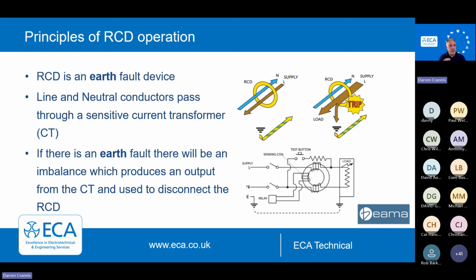And there are different levels that RCDs can handle with this, from the type AC, which is virtually nothing, up to type A's, B's, F's. They have more tolerance in that window. But that's essentially how an RCD works. With 30 milliamp RCDs, it's actually detecting at the 50 volt equivalent. And as you know, 50 volts across the heart is enough to stop your heart. So the 30 milliamp does come from that 50 volts calculation.